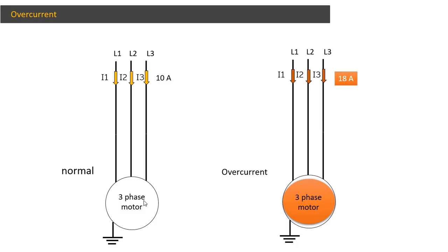But then, suddenly, out of nowhere, the current would be increased. Let's say, for example, a mechanical entanglement would appear in between your rotor and the stator, okay? And simply because of this, the current would suddenly be increased. And now, instead of 10 amperes, we're in fact dealing with 18. Now, such an overload might cause the coils inside your motors to burn up.